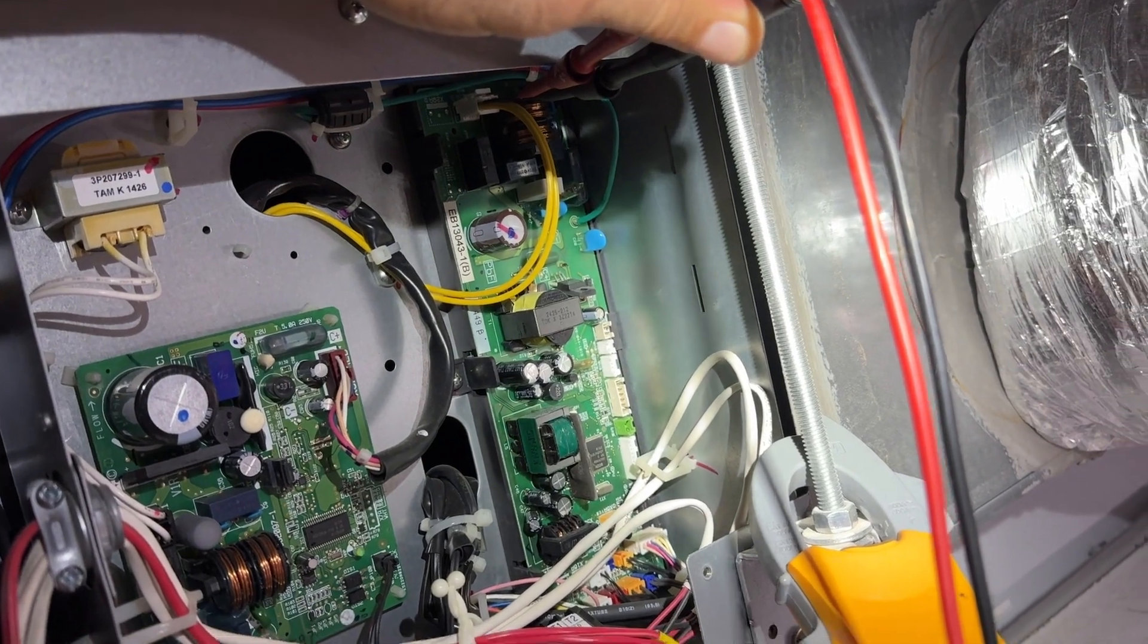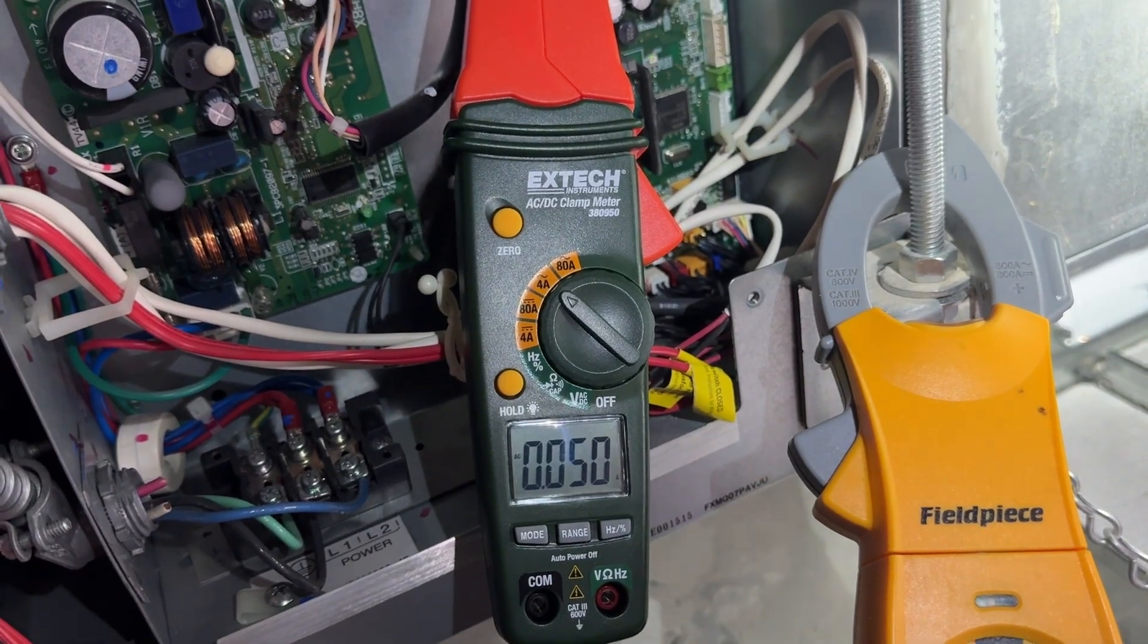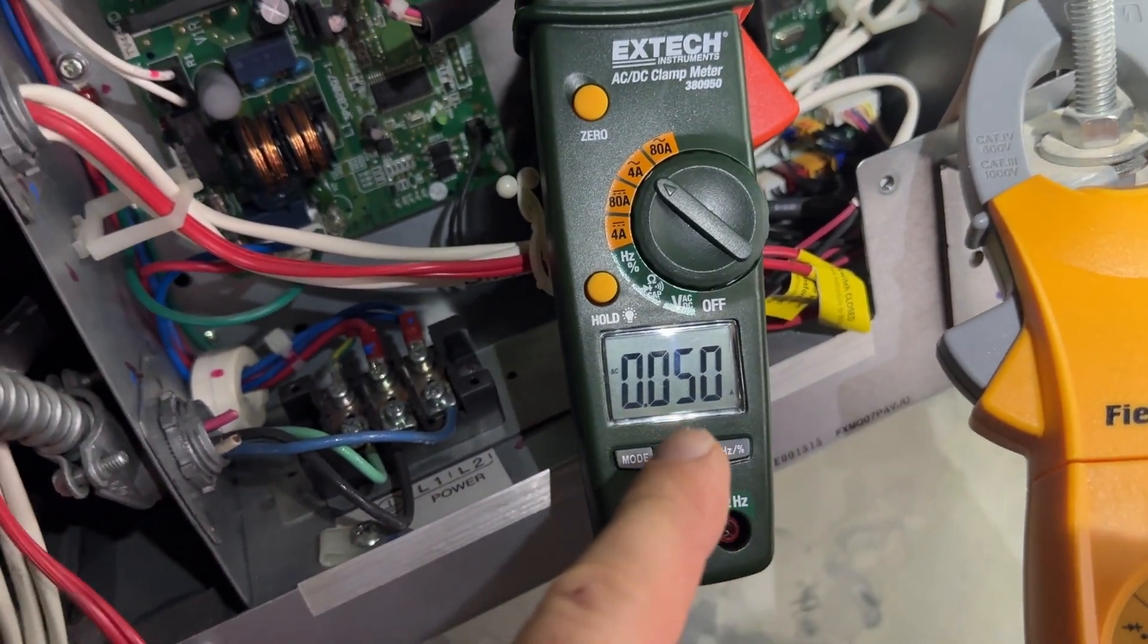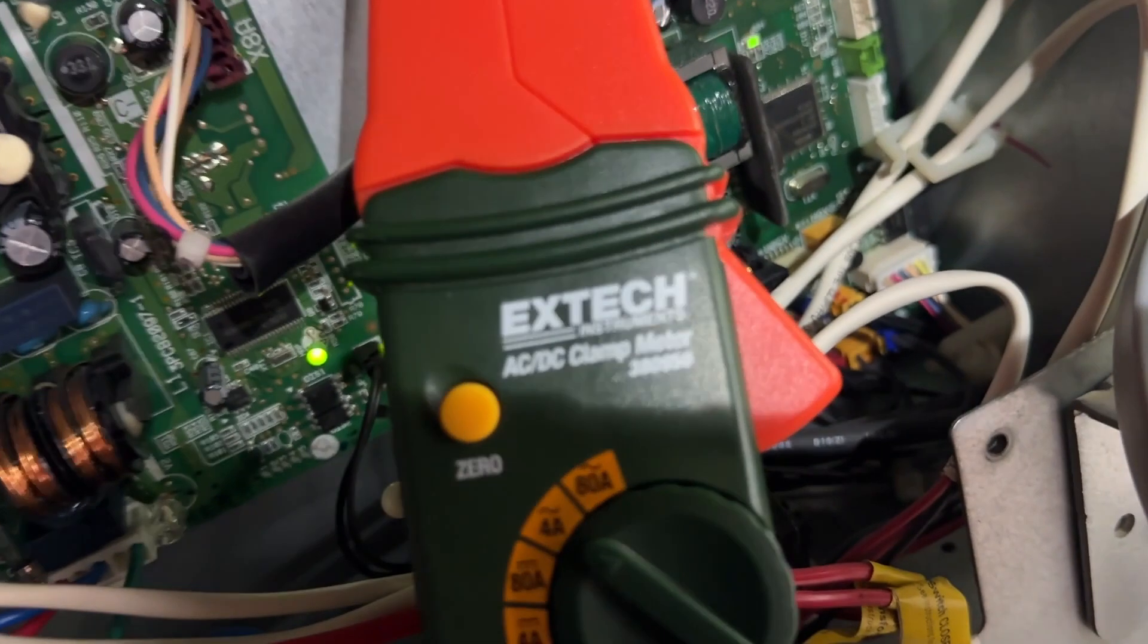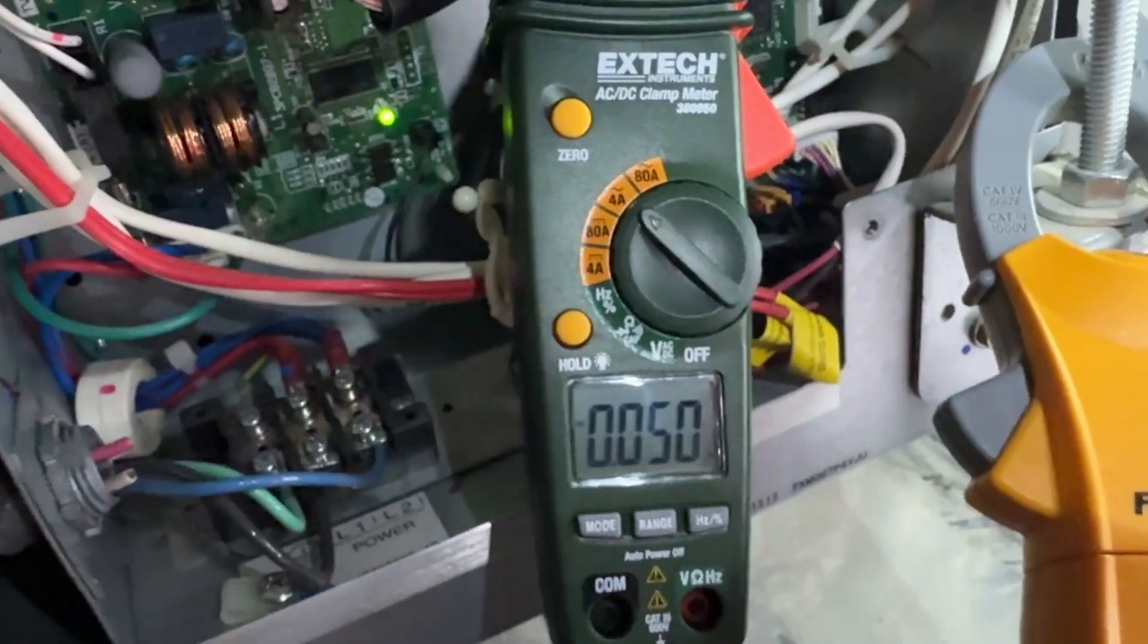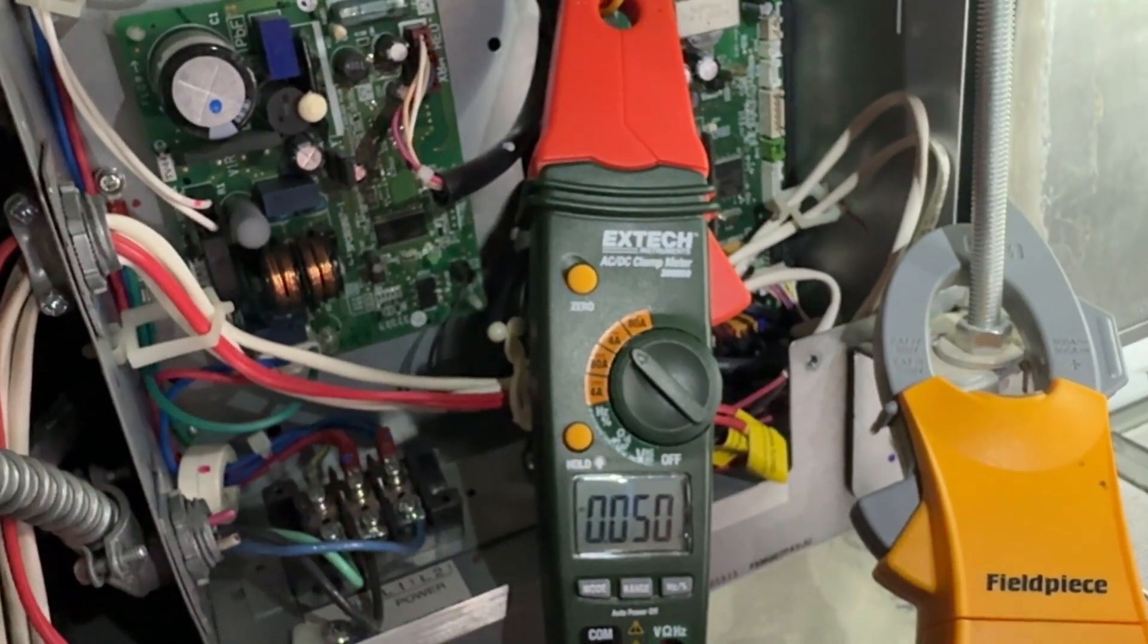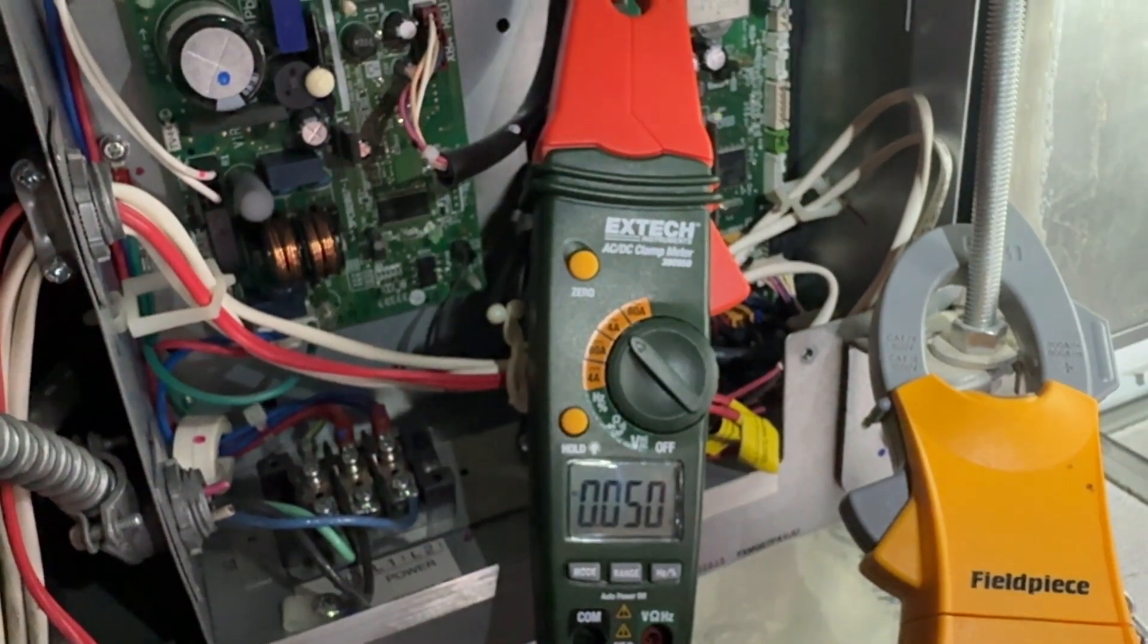Alright I do have voltage to the pump. They are line voltage pumps but there's one more thing we need to check. We need to check that the pump is actually using the voltage that it's being supplied with and it is. They run at about 50 milliamps. It took me forever to find a clamp meter that could read this stuff. This is it. I'll see if I can get that in focus. It's Extech. A lot of stuff on VRF systems is very low amperage high voltage so this meter has been awesome.